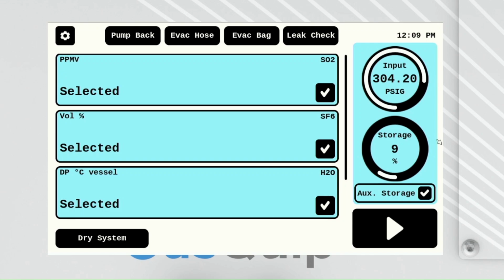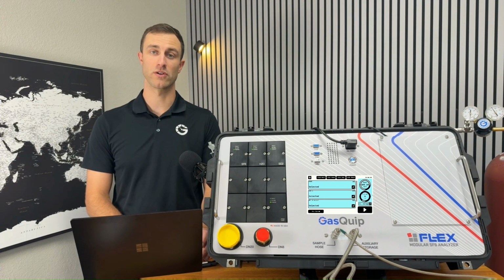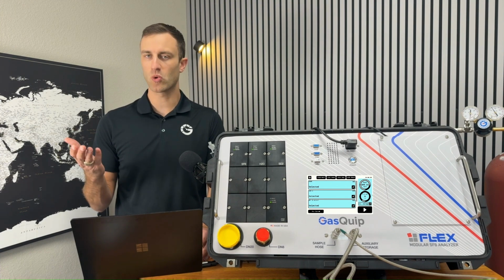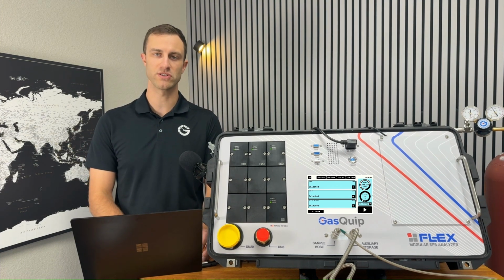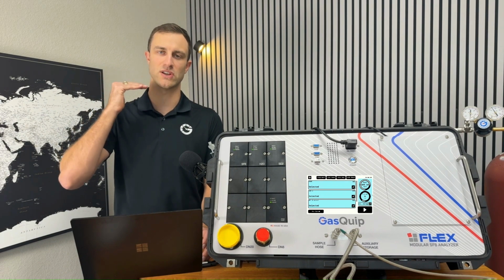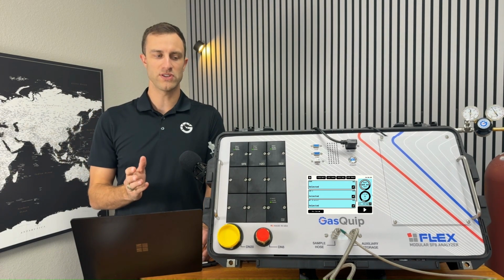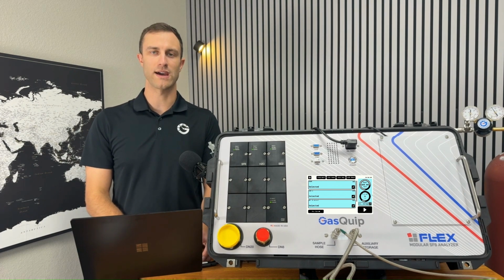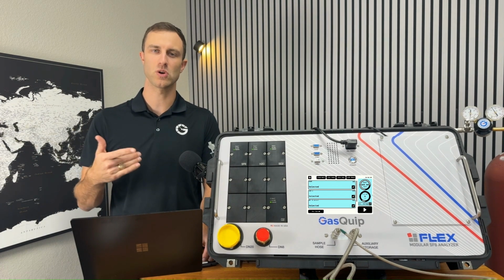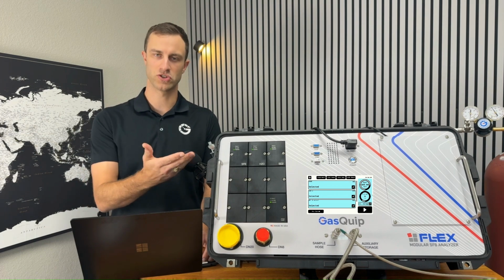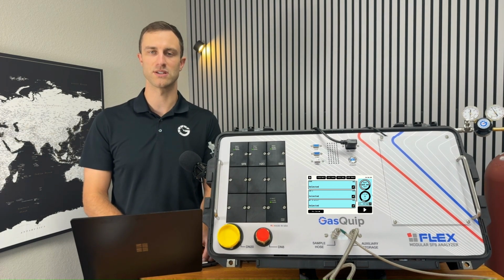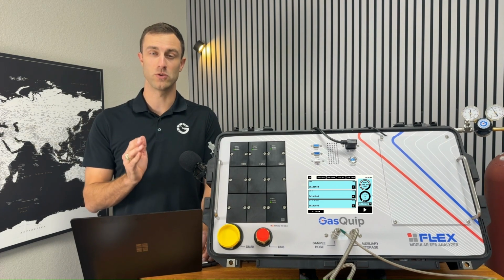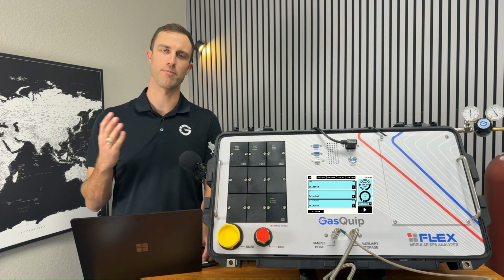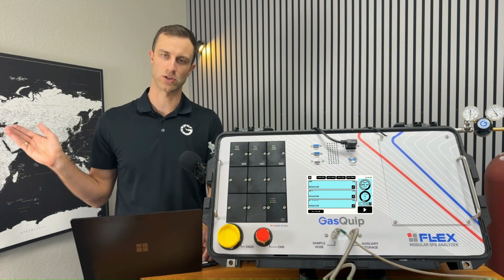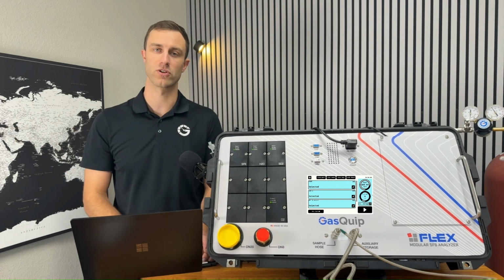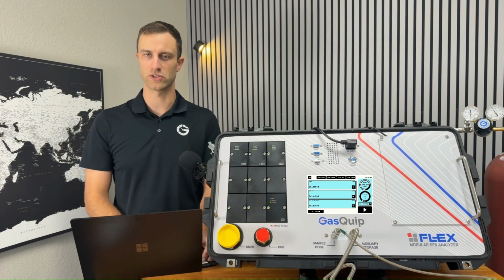Now, if you do have auxiliary storage hooked up like our gas recovery bag, you can expect to get an extra 20 to 25 measurements if you're running SO2, SF6, and H2O all together. The reason most people use a gas recovery bag is so that you don't have to run the pump back feature so often and empty your device, because the average Flex unit can hold 2 to 3 samples at a time with the internal storage. With the gas recovery bag, you don't have to run those pump back functions so often, so you can test a whole row of breakers or bottles or whatever it is, and have that extra storage.